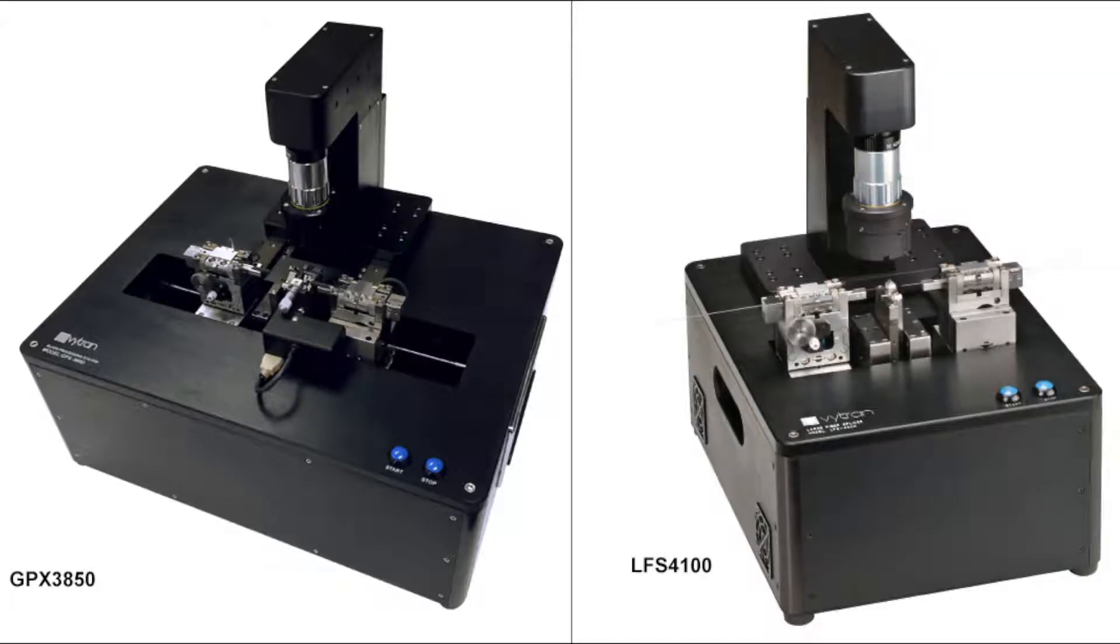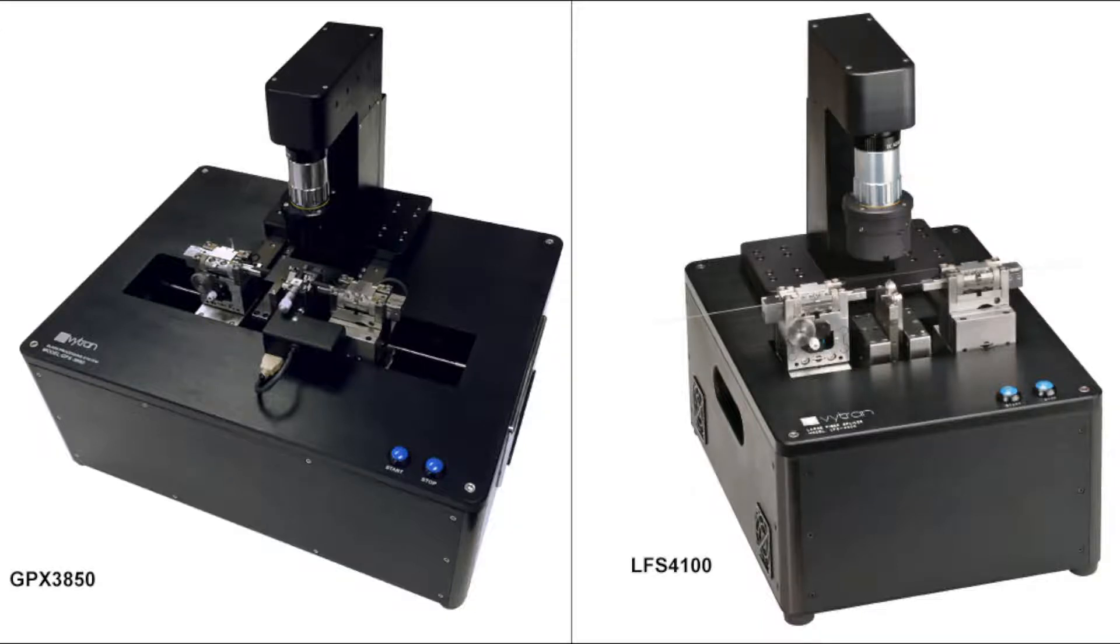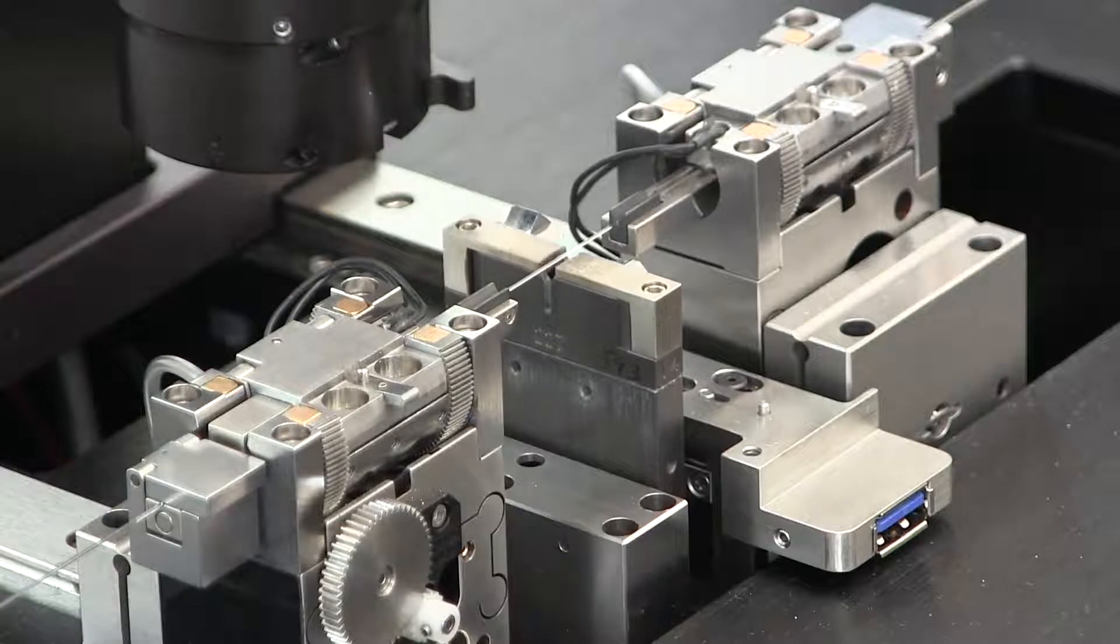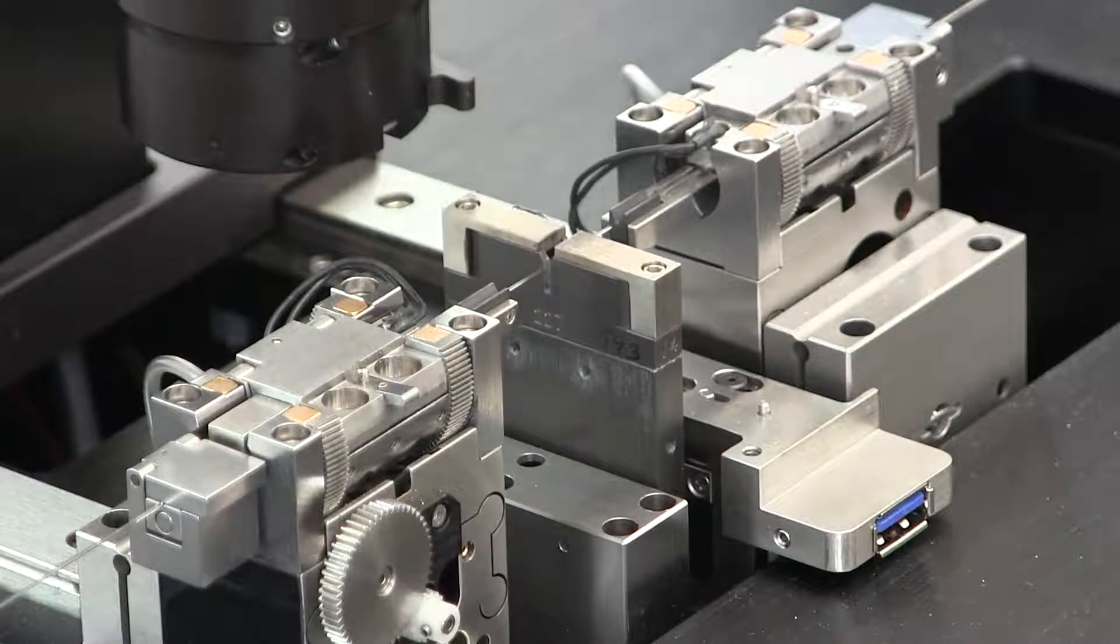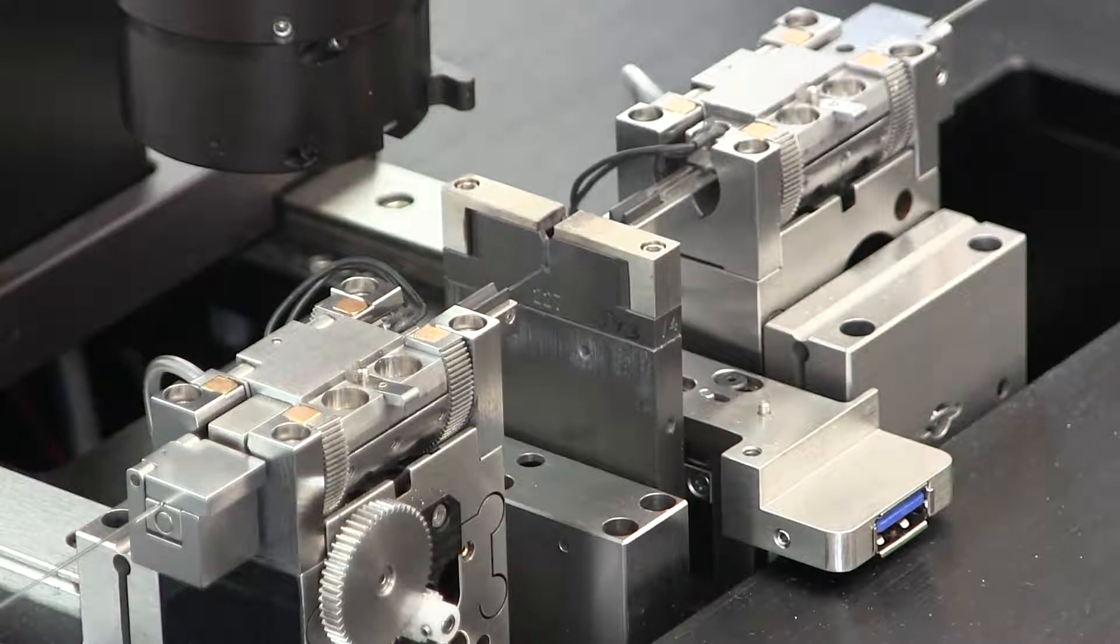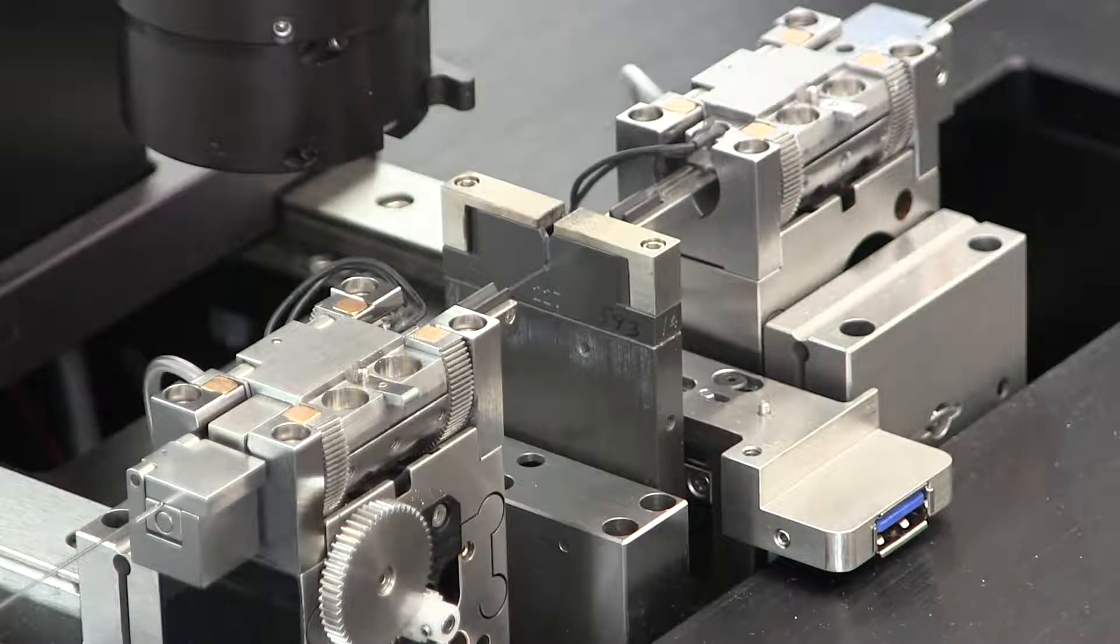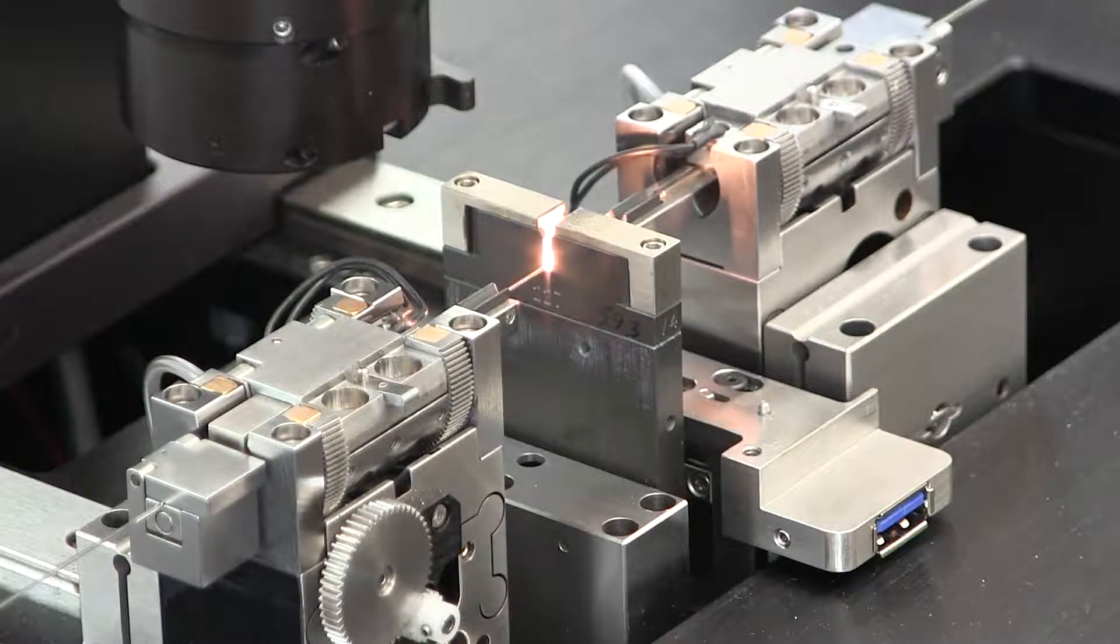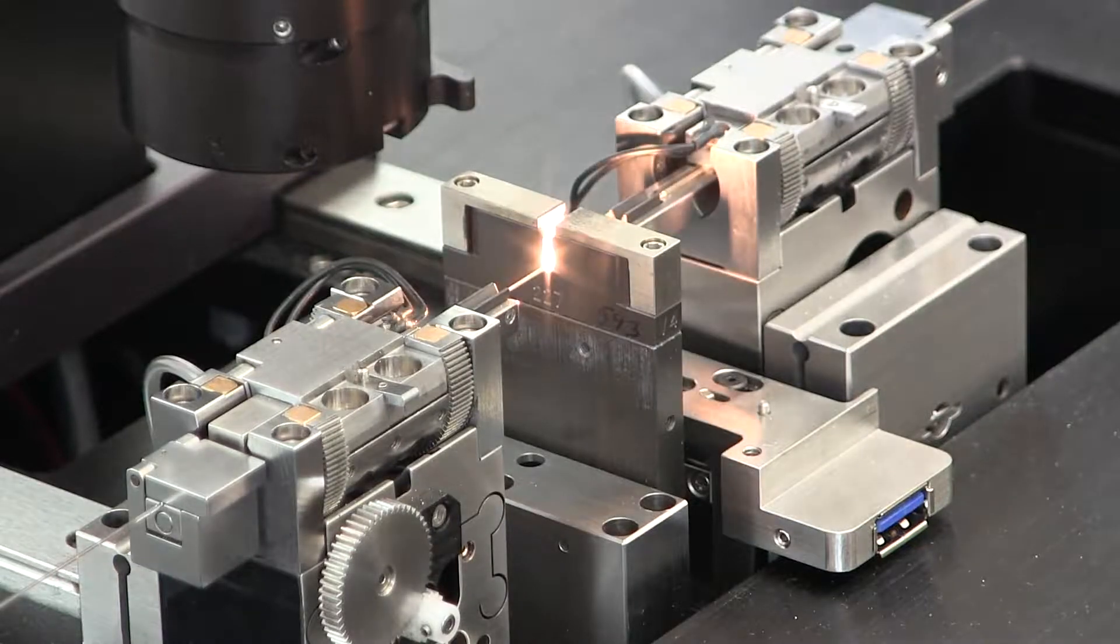GPX glass processors and LFS large fiber splicers use resistive filaments to process fibers. In order to assure consistent splice performance and thermal response of the filament over its lifetime, it must be normalized regularly. In this video, we will discuss how to normalize a filament.